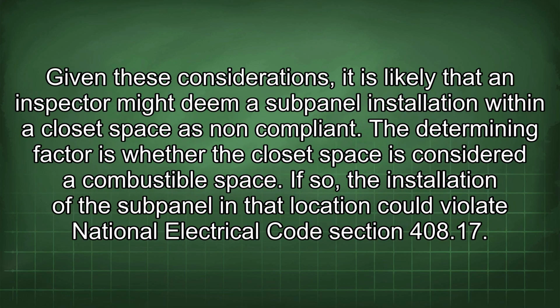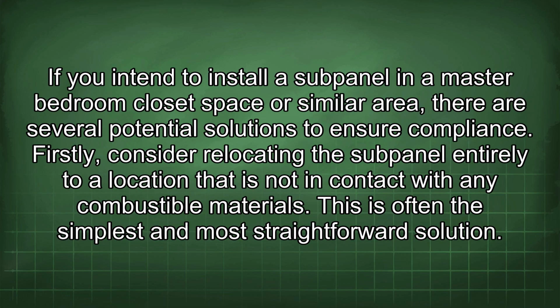Given these considerations, it is likely that an inspector might deem a subpanel installation within a closet space as non-compliant. The determining factor is whether the closet space is considered a combustible space. If so, the installation of the subpanel in that location could violate National Electrical Code Section 408.17. If you intend to install a subpanel in a master bedroom closet space or similar area, there are several potential solutions to ensure compliance. Firstly, consider relocating the subpanel entirely to a location that is not in contact with any combustible materials. This is often the simplest and most straightforward solution.